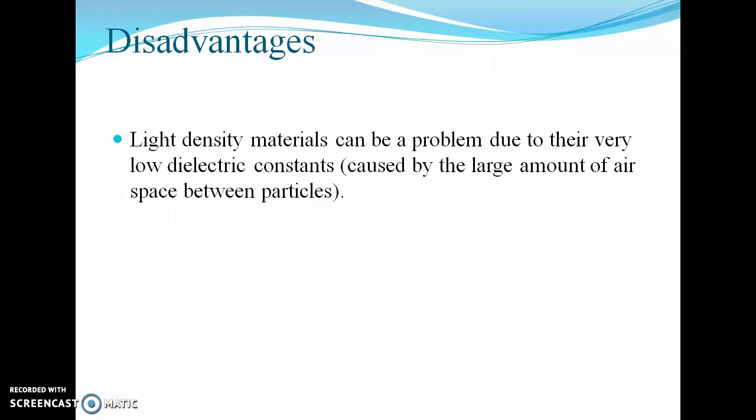Disadvantages are: light density material can be a problem due to its very low dielectric constant. For materials with low density, the measurement of level is a bit difficult because they have a low dielectric constant, which is caused by the large amount of air space between the particles. That's why there is a problem with measuring the levels.